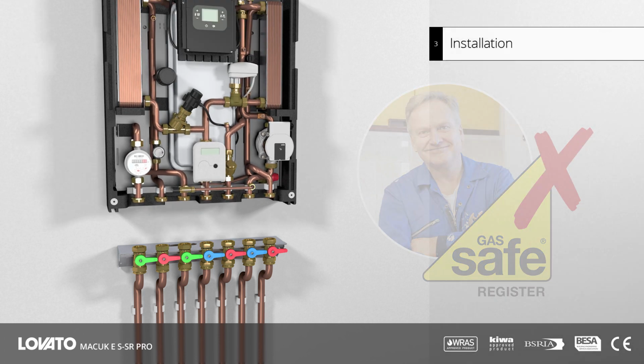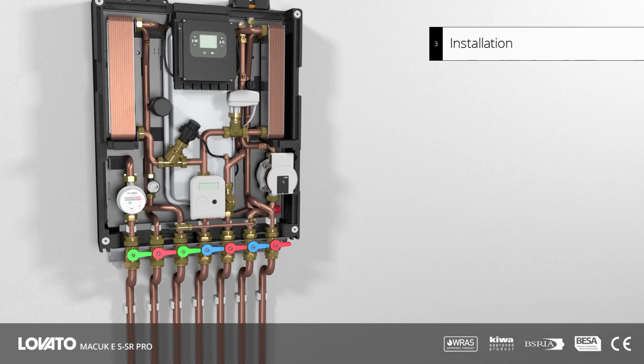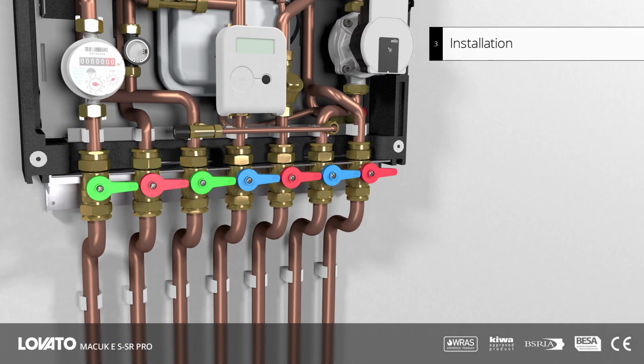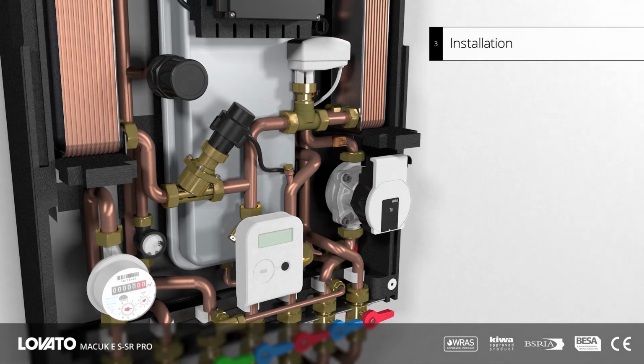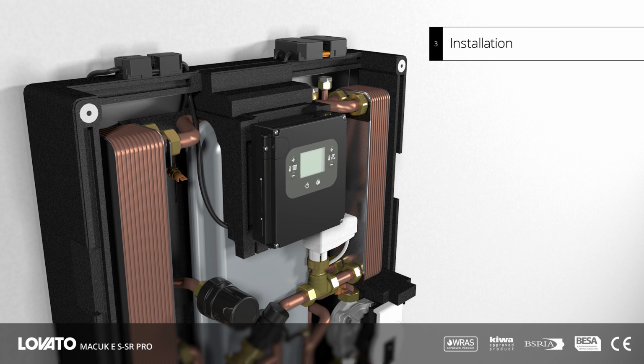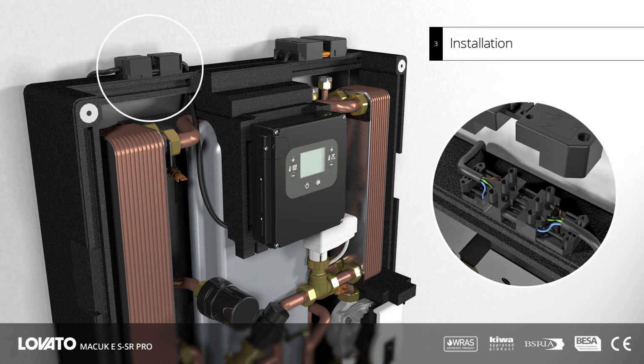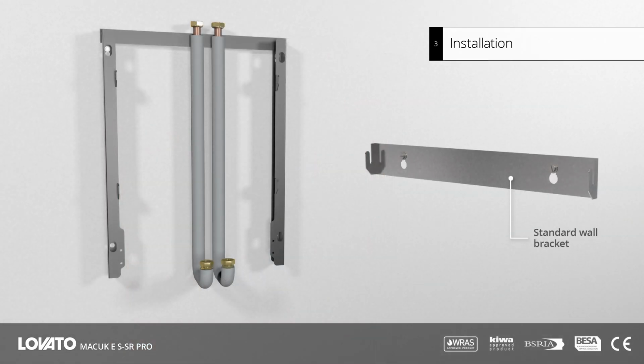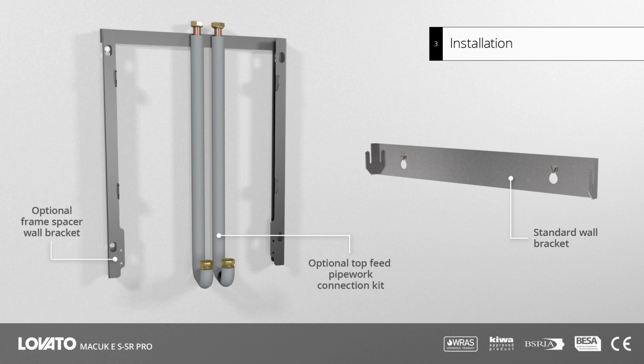The heat interface unit is hung from a wall-mounted bracket and, once aligned, connects to the first fix bracket via 7 couplings. To complete the installation, connect to the mains power via the terminal connection block. For a top feed supply, an optional pipework connection kit and frame spacer brackets are available.